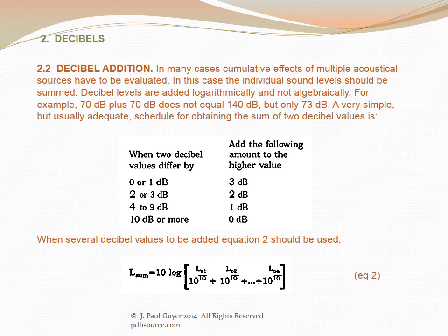Decibel levels are added logarithmically, not algebraically. For example, 70 dB plus 70 dB equals 73 dB, not 140 dB. A simple schedule for summing two decibel values: when they differ by 0–1 dB, add 3 dB to the higher value; differ by 2–3 dB, add 2 dB; differ by 4–9 dB, add 1 dB; and if they differ by 10 dB or more, add 0 dB to the higher value.